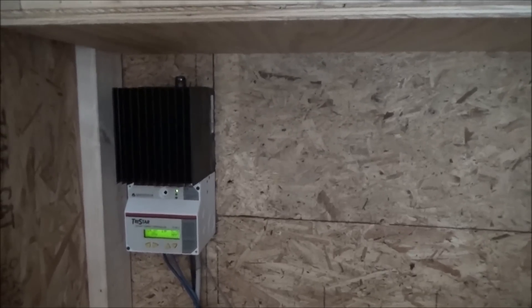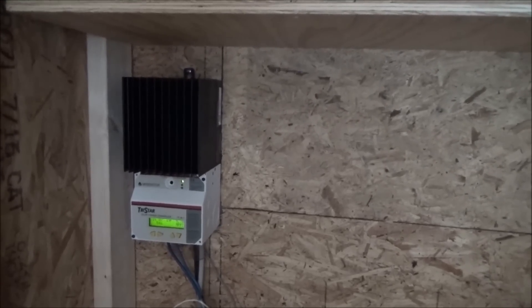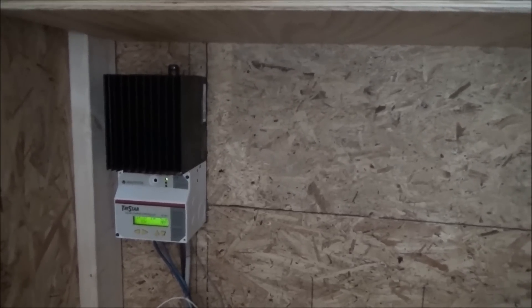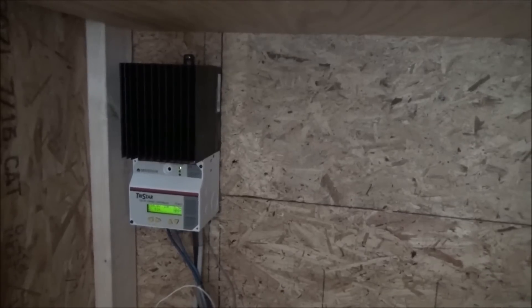I do think they're going to power the tiny house very nicely. I'm going to do some research on the specific gravity and the voltage at this temperature for the forklift batteries because it's only 19 degrees. I'm thinking they're going to settle to about 12.3–12.4 volts later on today. At 5–6 amps coming in, that's nothing for these 525 amp-hour battery cells — that's about 1/100th of the capacity, so it would take about 100 hours to charge them at that rate. It's very important to watch your total power coming into your house and compare it with total power going out to ensure you have enough coming in each day.